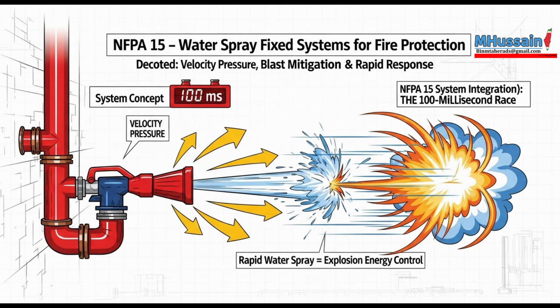Yeah, this is non-negotiable blast mitigation design. First, the system actuation valves, the main controls, have to be located remotely, at least 50 feet away, and they need to be housed in structures built to withstand significant overpressure. How significant? The standard specifies these structures must be blast resistant, designed for at least 3 psi static overpressure. 3 psi static. Okay, that's serious protection, designed so someone could still manually operate the system even after an initial event. That's the idea. Protect the controls, protect the human interface.